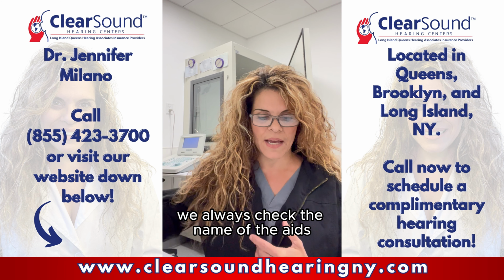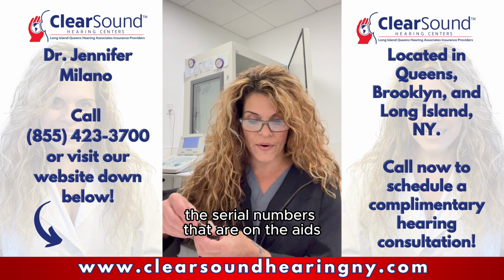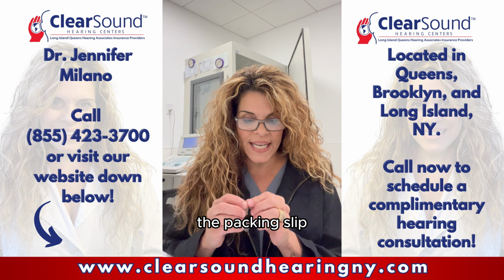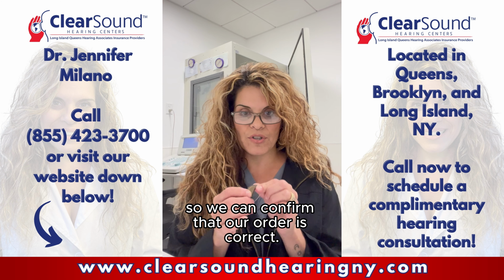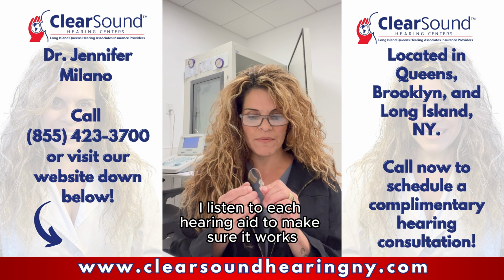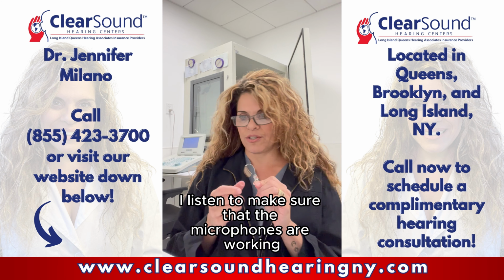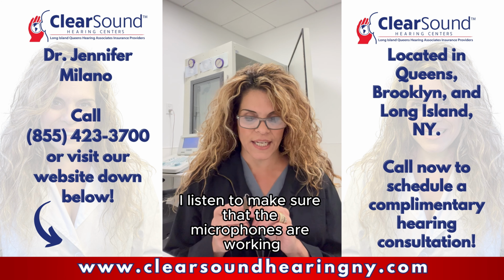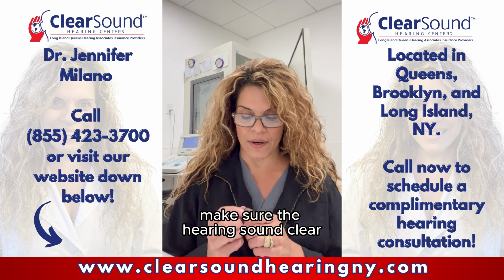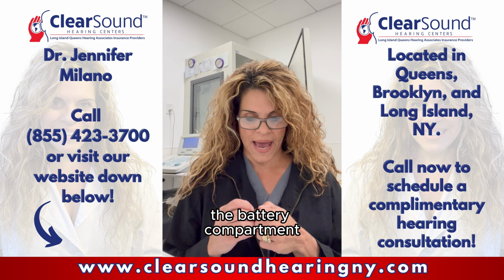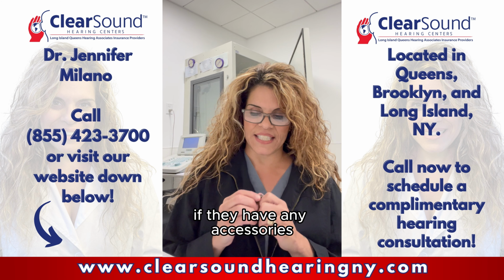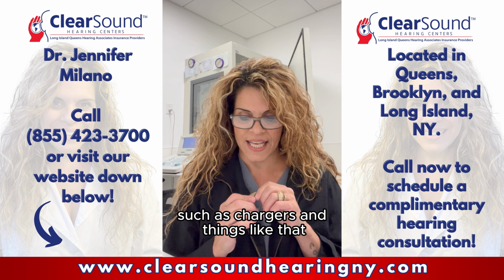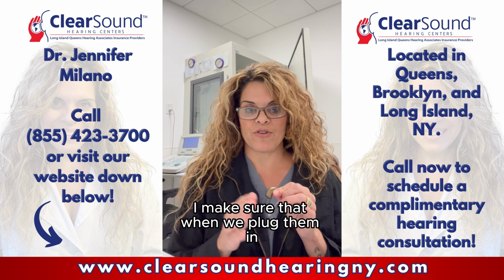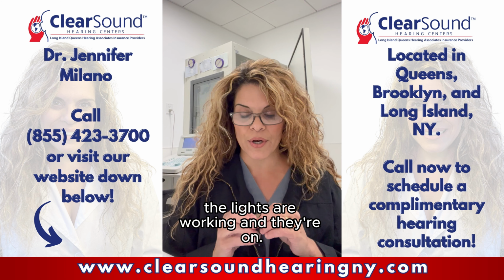We always check the name of the aids, the serial numbers that are on the aids, and the packing slip, so we can confirm that our order is correct. I listen to each hearing aid to make sure it works. I listen to make sure that the microphones are working. I make sure the hearing aids sound clear. Make sure everything's working, the battery compartment. If they have any accessories such as chargers and streamers, I make sure that when we plug them in, the lights are working and they're on.